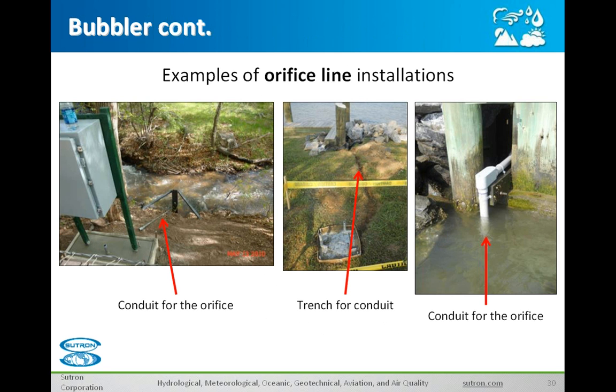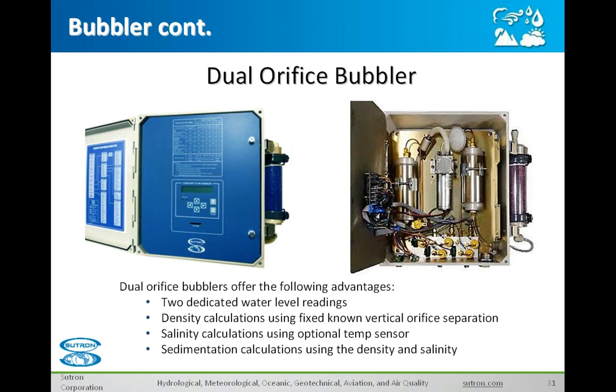The next slide shows what it looks like when it's terminated out in the water. You see the black tubing — that's your orifice line down the conduit. There's also an orifice cap that connects onto your conduit, and the orifice line terminates into that cap through a copper fitting, protecting the orifice line from debris. If you get any sort of leak in that line, it will certainly disrupt your data quality. Next, you have pictures of actual orifice line installations — one shows conduit going in the water mid-installation, another shows a trench being run for the conduit, and the third shows the completed installation with the conduit running into the body of water.